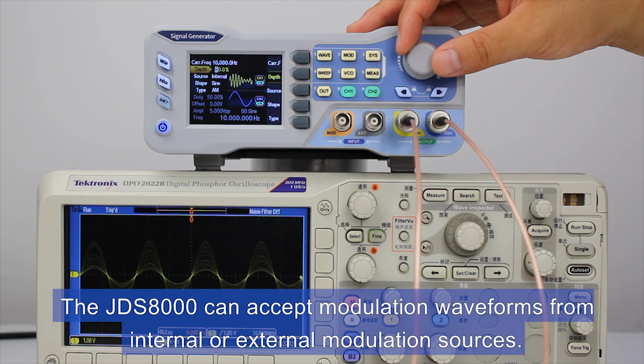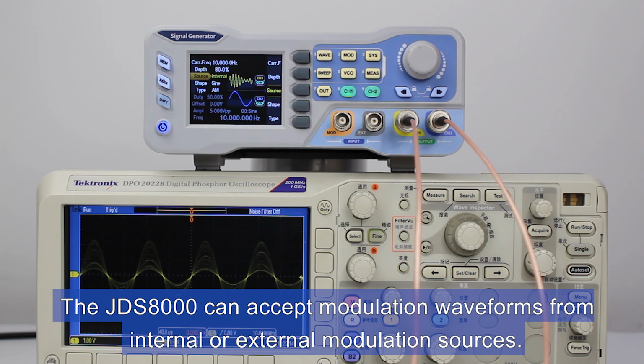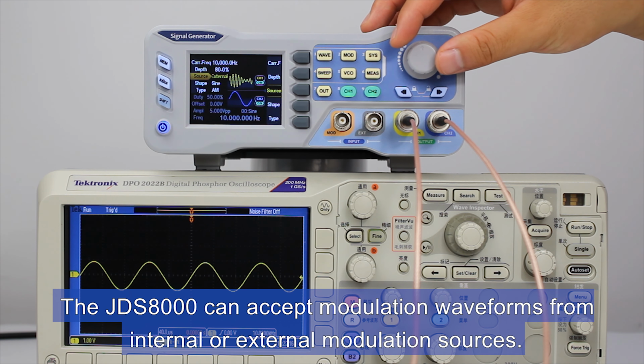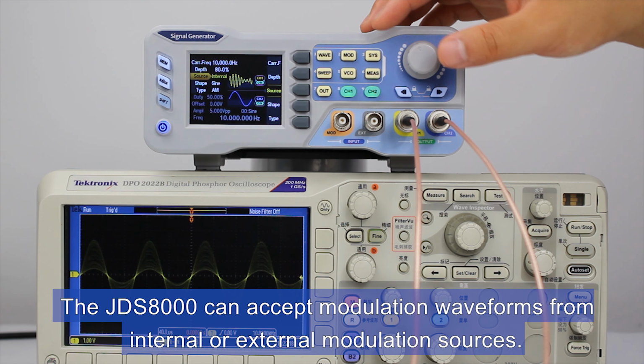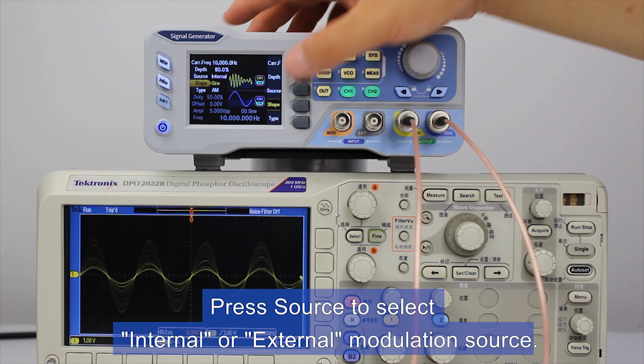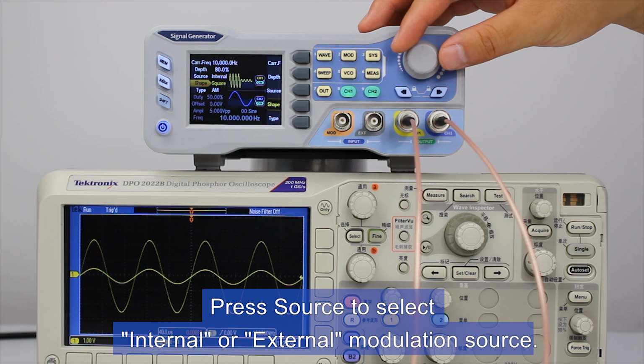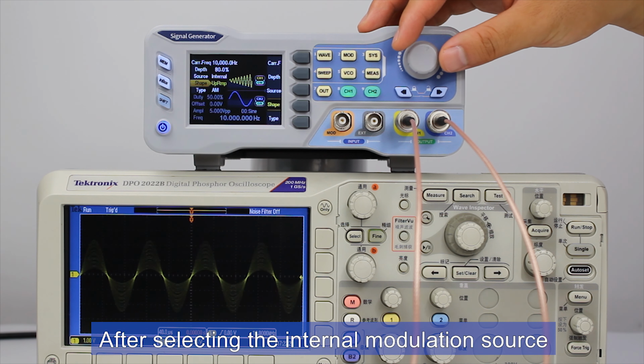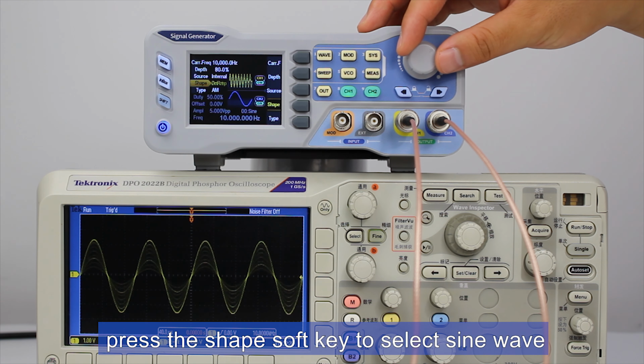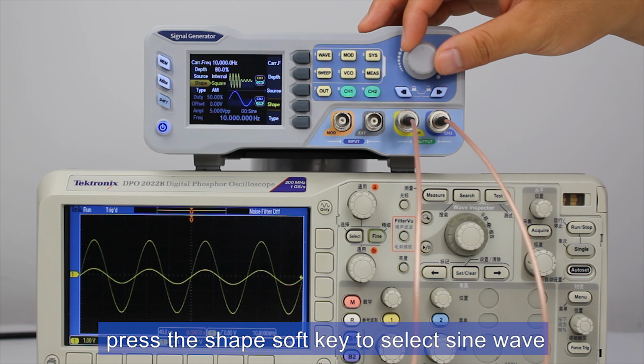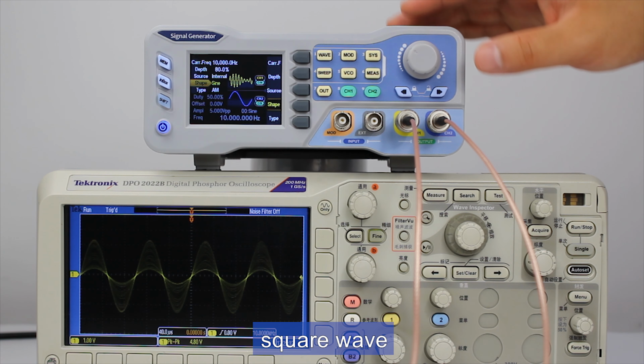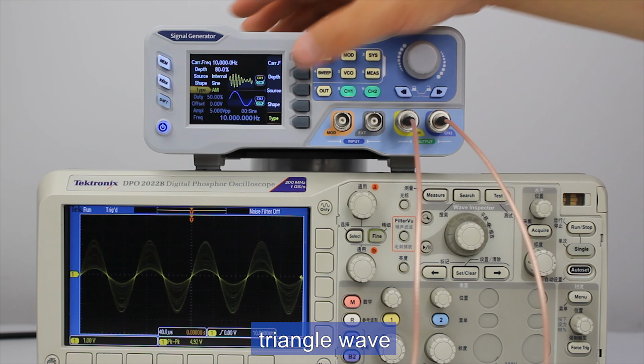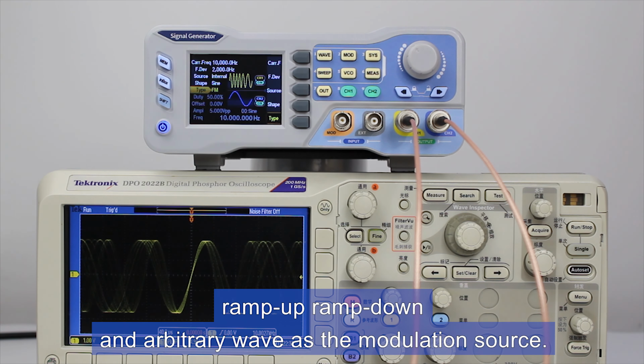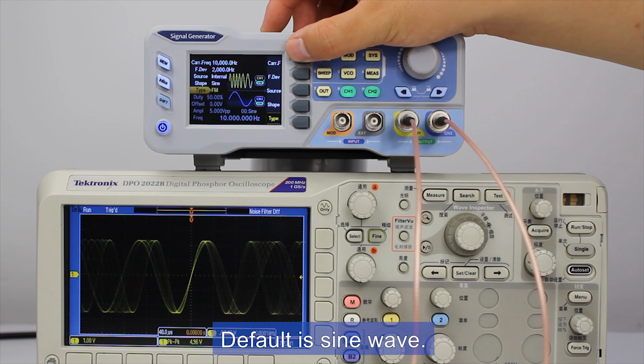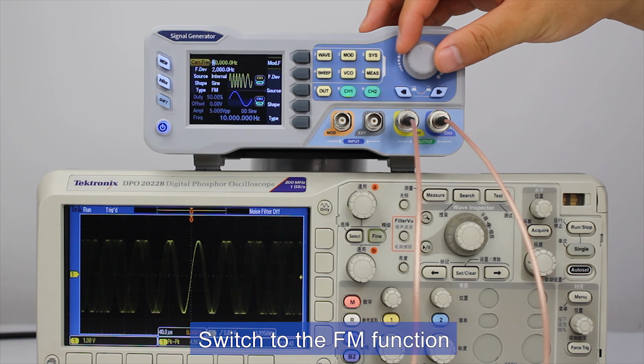The JDS8000 can accept modulation waveforms from internal or external modulation sources. Press Source to select internal or external modulation source. After selecting the internal modulation source, press the Shape soft key to select sine wave, square wave, triangle wave, ramp up, ramp down, and arbitrary wave as the modulation source. Default is sine wave. Switch to the FM function.